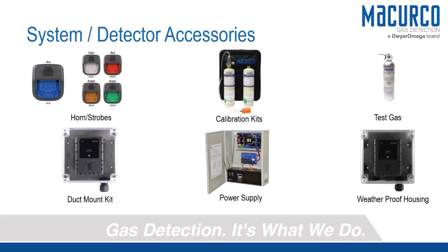On the bottom you have duct mount kits, power supplies, and weatherproof housing kits—those are all just accessories. We're starting to see the weatherproof ones (WHK) used quite a bit in parking garages due to spray downs or wash downs. The power supply is just a piece of equipment to power the sensors out in the field—the panel we offer doesn't have enough power to run many sensors, so using one of these is pretty critical.